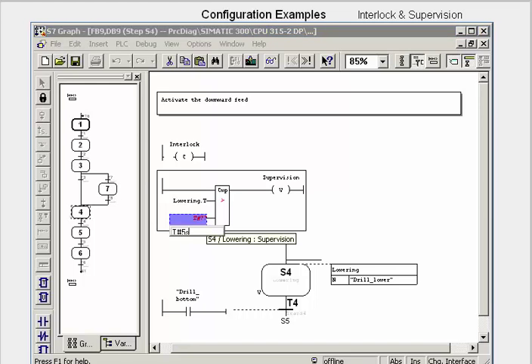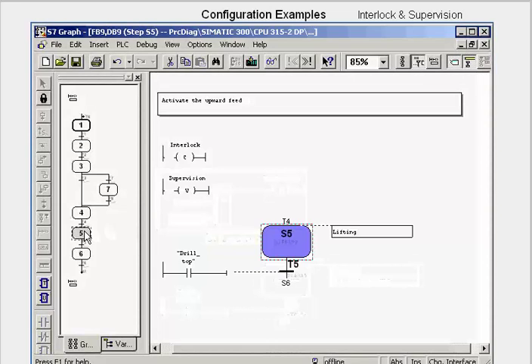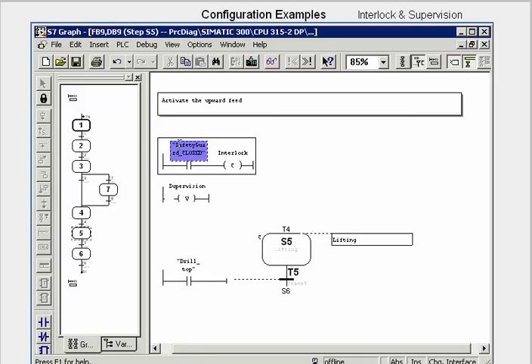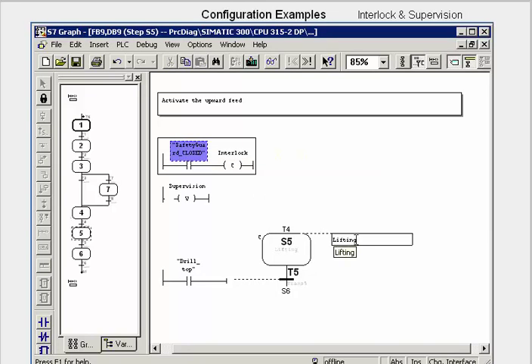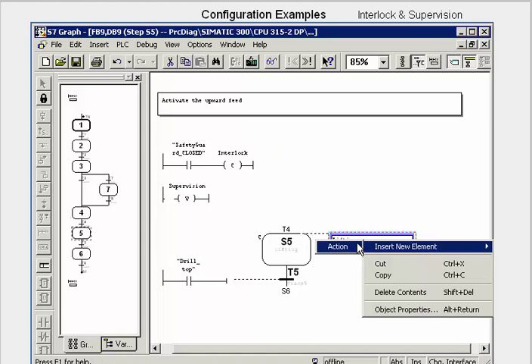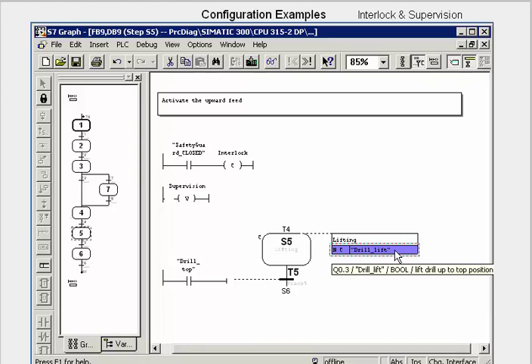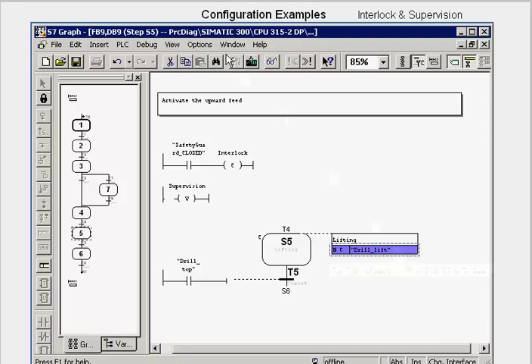Step 4 is now marked with a V. An interlock means that a message is triggered when the interlock conditions are no longer fulfilled, and all output actions linked with the interlock are blocked. To build an interlock into step 5, we select the step and in the relevant wildcard, we insert an AND operation, which we assign to the safety guard closed address. Step 5 is marked with a C. We now link the interlock to the action DRILL LIFT. If the safety guard is opened while step 5 is active, the command output is blocked.